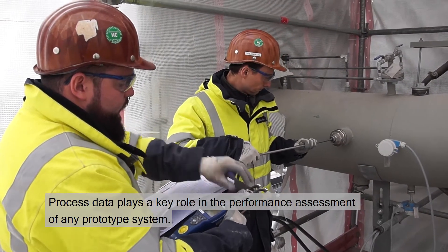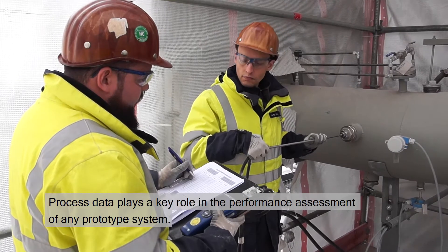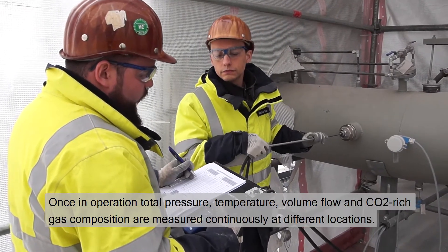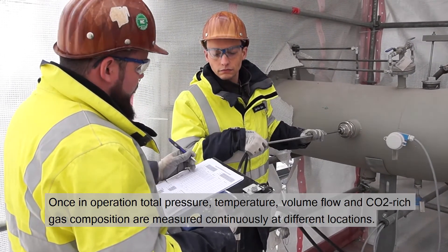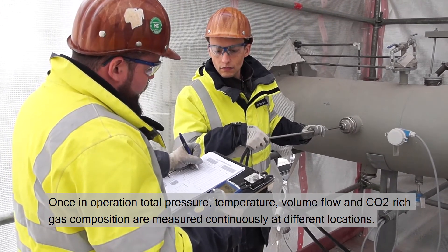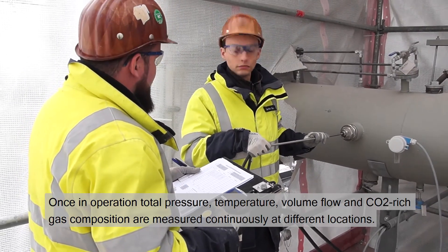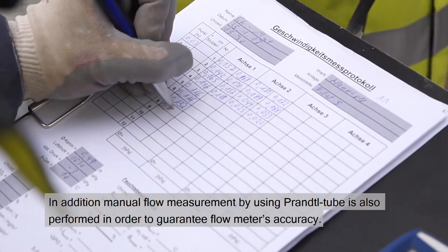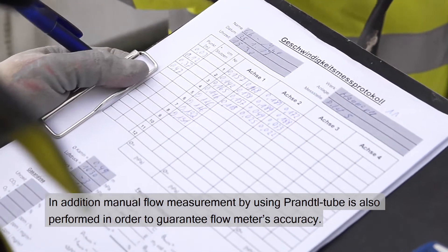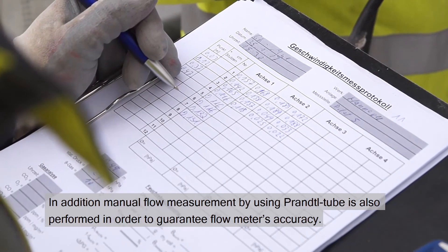Process data plays a key role in the performance assessment of any prototype system. Once in operation, total pressure, temperature, volume flow, and CO2-rich gas composition are measured continuously at different locations. In addition, manual flow measurement using a Prandtl tube is also performed in order to guarantee flow meter accuracy.